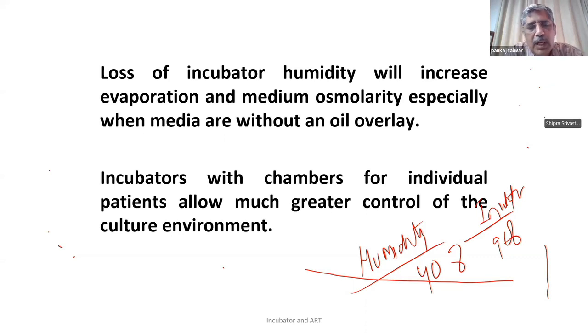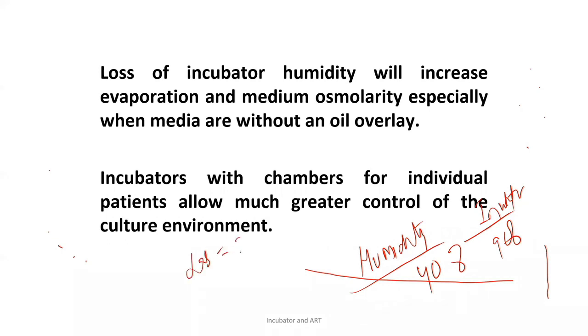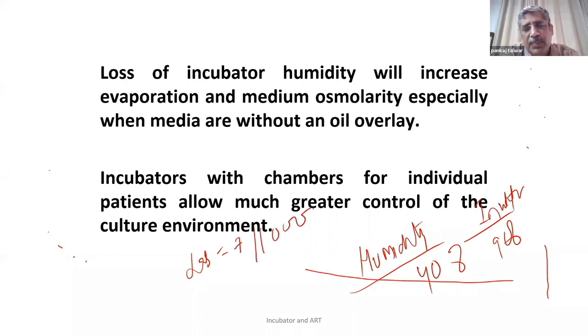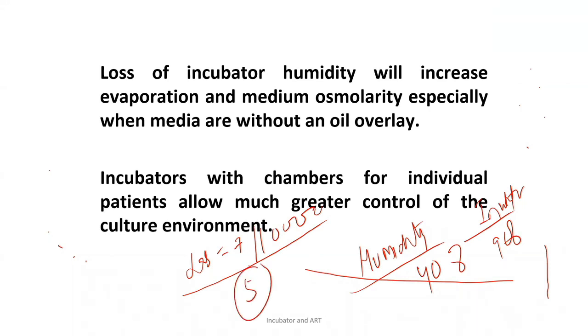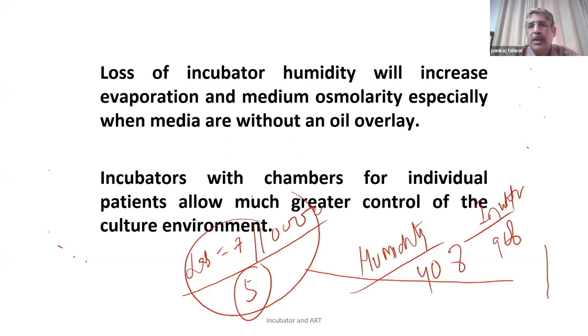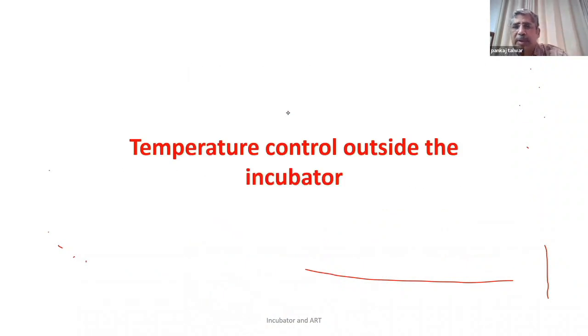So just remember that the class of air in the lab is Class 10,000, ISO 7. And the class of air in the incubator is Class 5. Remember this. When we open the incubator door, hot air comes out, the temperature will fall, alkalosis will occur, humidity will fall, but one more thing will occur: dirty air will go inside. The incubator has to work at ISO 5, and the air which goes inside is ISO 7. So incubators can become contaminated. This is what I want to tell you here.